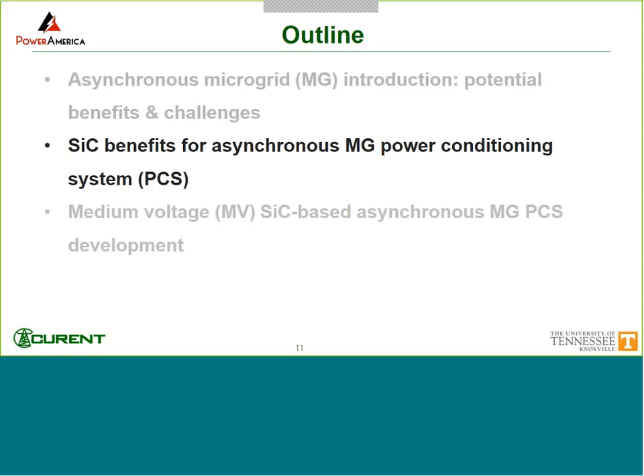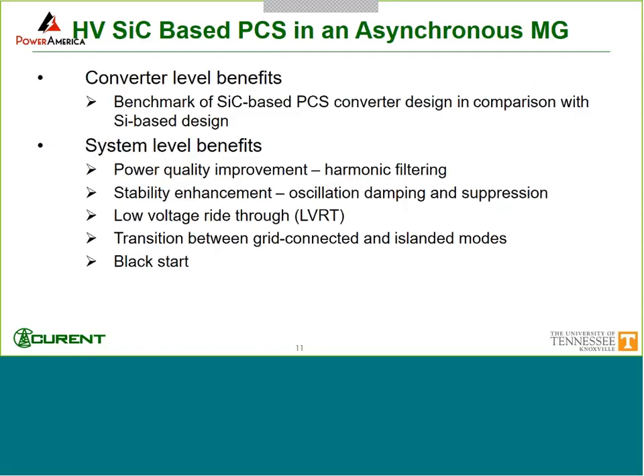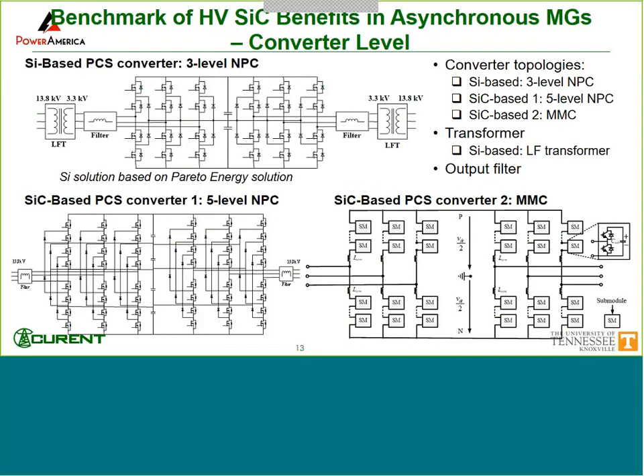An example I'm showing here is a 10 kV silicon carbide MOSFET. The benefits can be grouped into two. First is at the converter level. We have conducted some benchmarking of silicon carbide-based PCS converter designs in comparison with the silicon solution I just showed you. The system level benefits include power quality improvement, like harmonic filtering, stability enhancement, oscillation damping, low voltage ride-through, transition between grid connected and islanded modes, and also black start. So let me start with the benchmark of the converter.